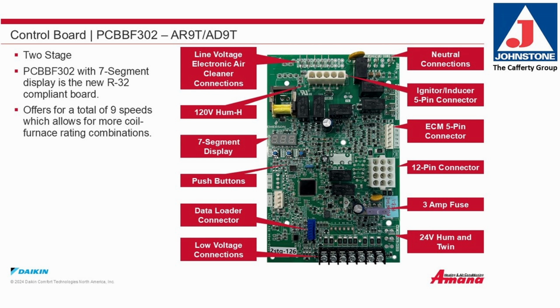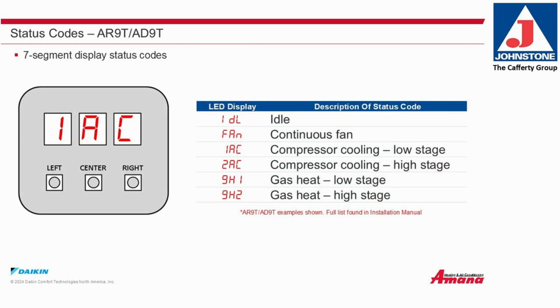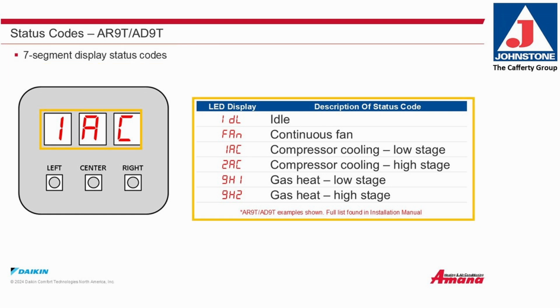Control board PCB BF302, two-stage. The PCB BF302 with a 7-segment display is the new R32 compliant board. It offers a total of 9 speeds, which allows for more coil furnace rating combinations. Status codes. Here are some examples of the 7-segment display status codes. IDL means idle. FAN, continuous fan. 1 AC, compressor cooling, low stage. 2 AC, compressor cooling, high stage.